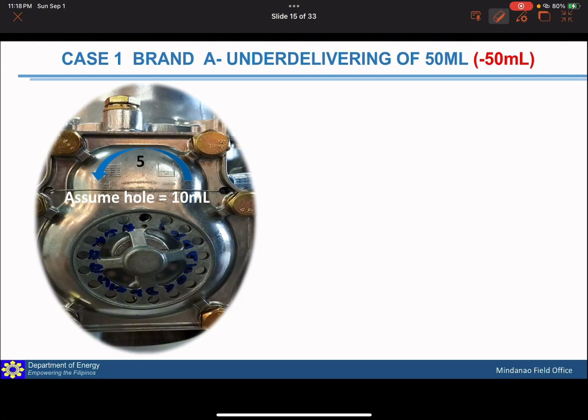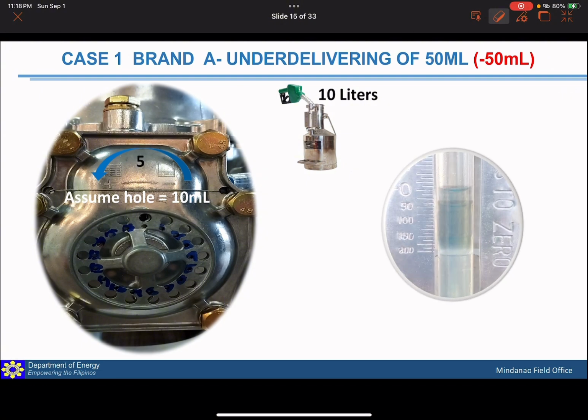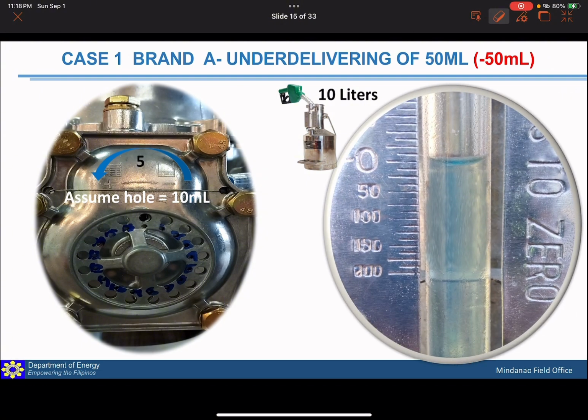So kasi under tayo ng negative 50. Nag-under tayo ng negative 50 dun sa first example. So what we need to do is to rotate the mechanical wheel clockwise 5 times. 5 holes ang kanyang distance. After natin mag-adjust, mag-dispense tayo ulit ng 10 liters. Then after 10 liters, we need to read the calibrating bucket. This is now the new reading.